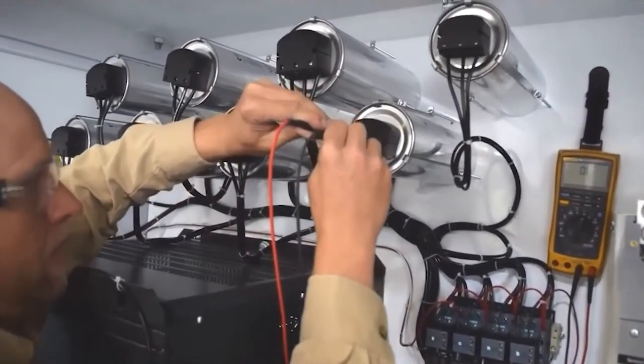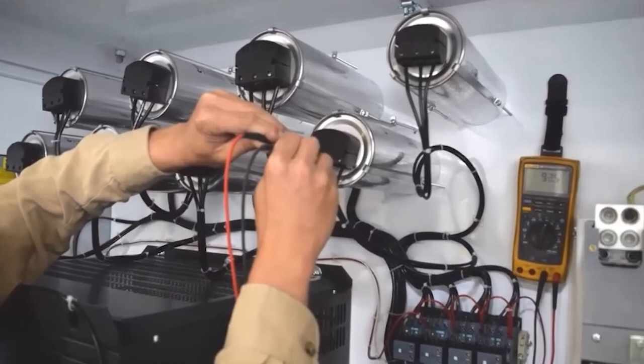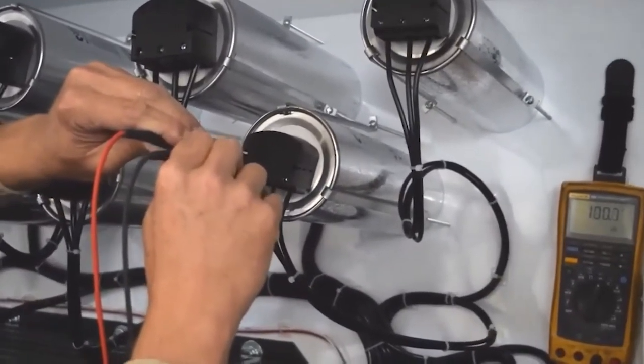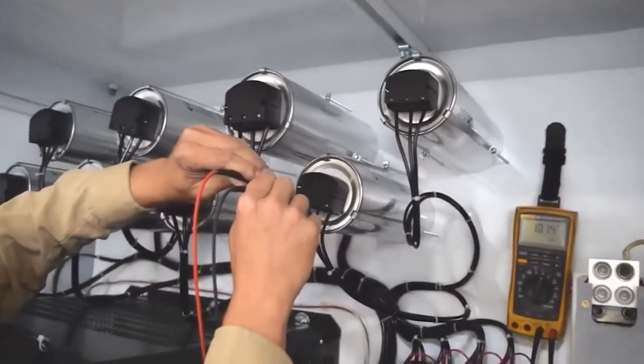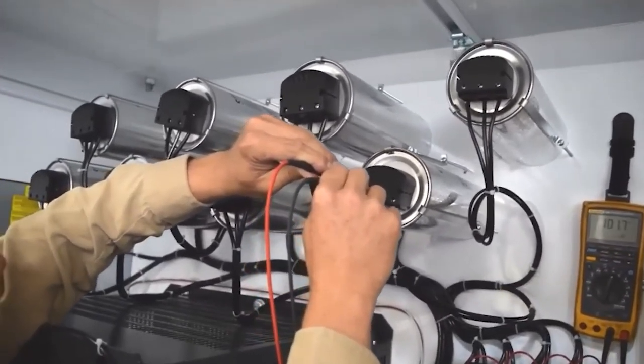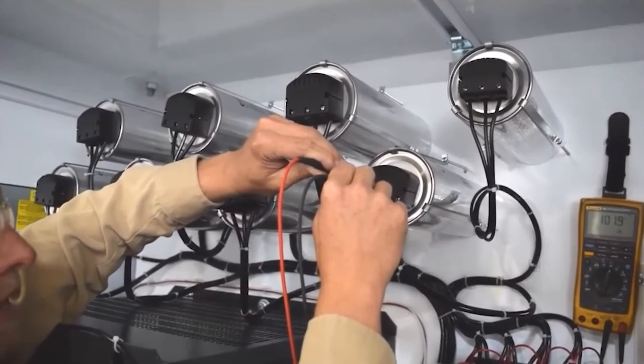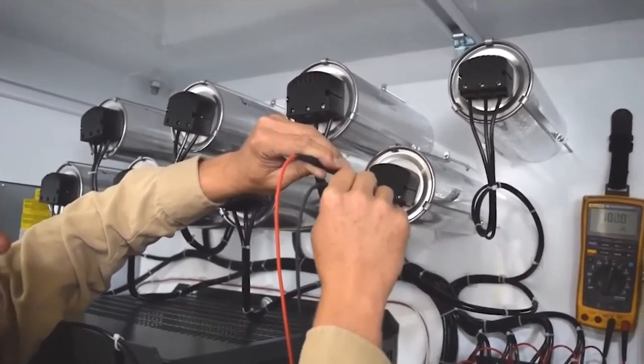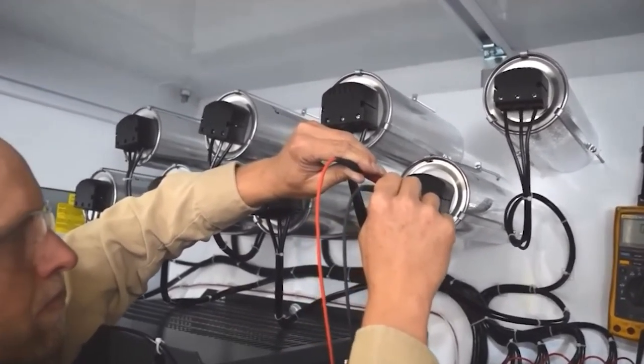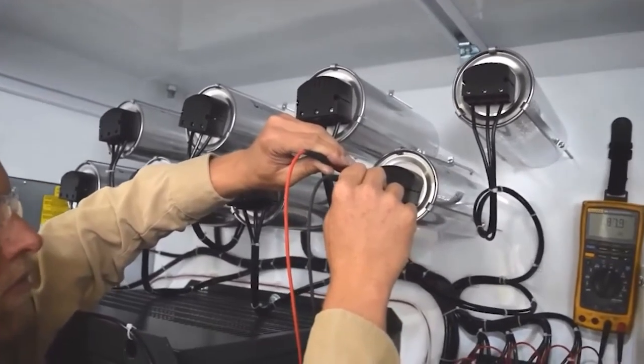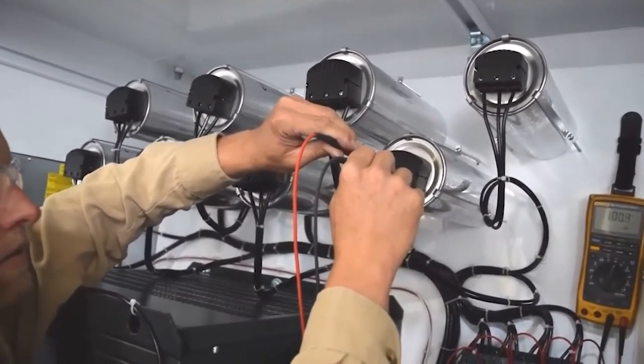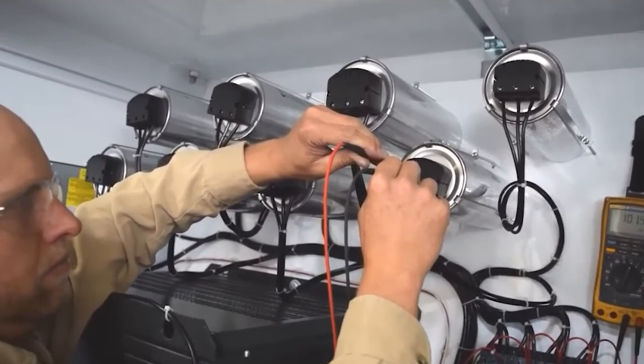So I just got done measuring that capacitor. I'm moving to the next one. Now these two capacitors are the same size, so I should get the same reading. It's another good indicator when you're inside a cabinet with a lot of capacitors in it. You can compare one from another to make sure capacitor A is going to match up with capacitor B. And if they're all the same kVAR, they all should have a real similar reading.